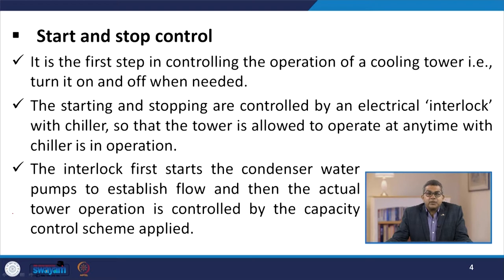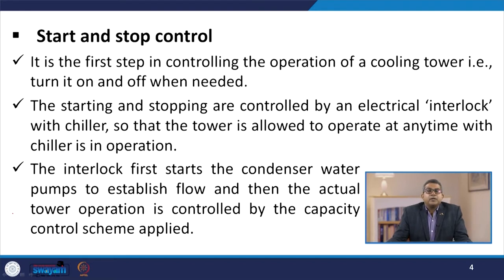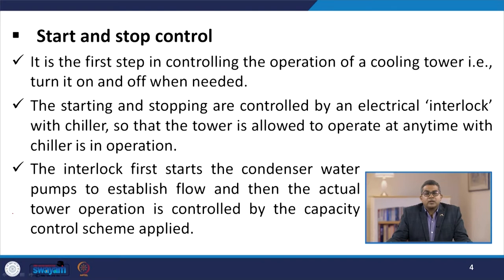Let us start with the start and stop control. This is the first step in controlling the operation of the cooling tower — turning it on or off when needed. The starting and stopping are controlled by the electrical interlock with the chiller, so that the tower is allowed to operate only when the chiller is in operation. The interlock first starts the condenser water pump to establish flow, and then the actual tower operation is controlled by the capacity control scheme applied to that particular cooling tower.